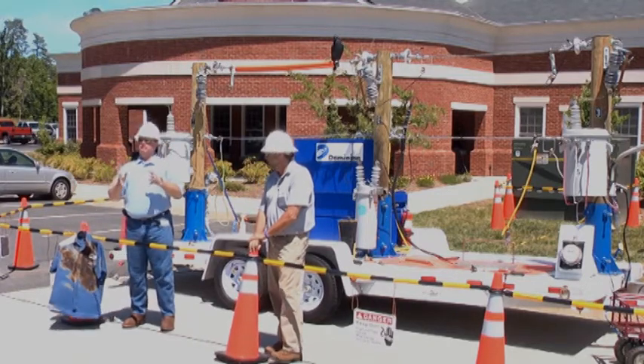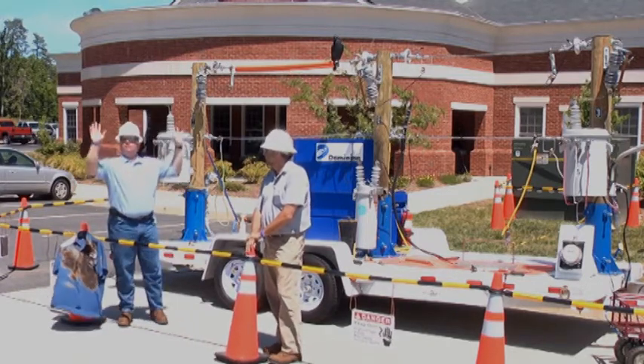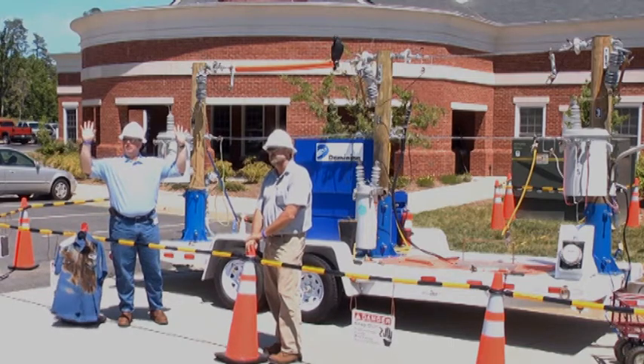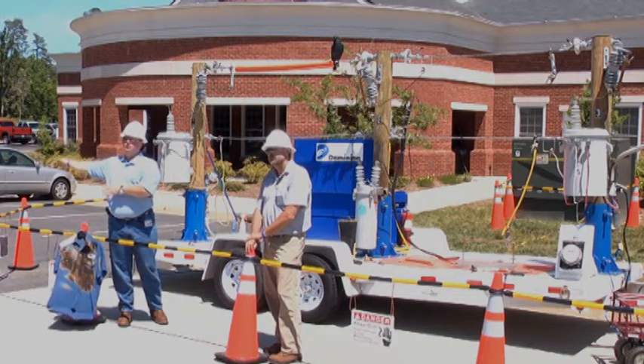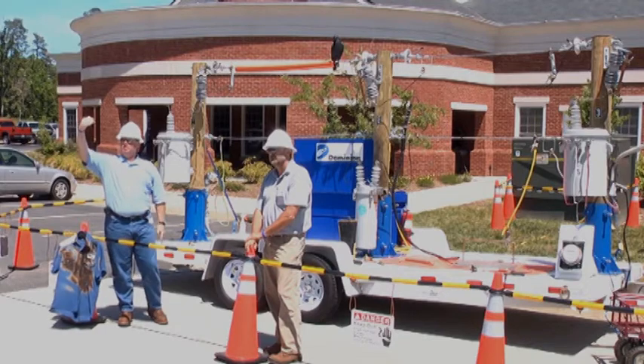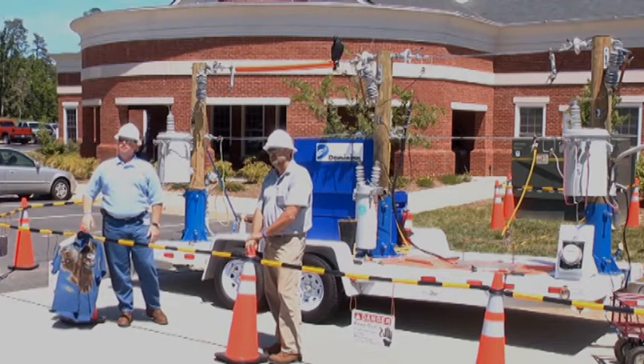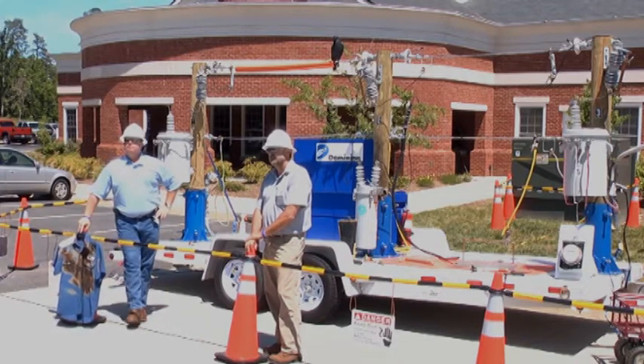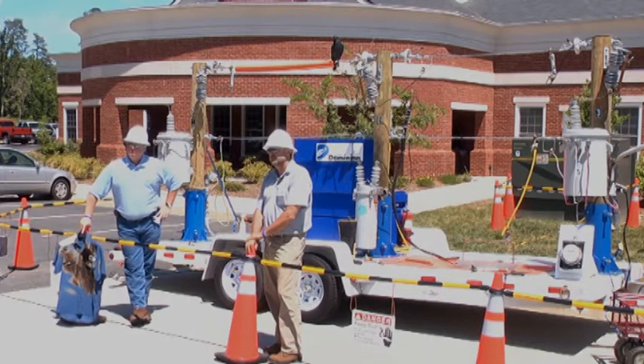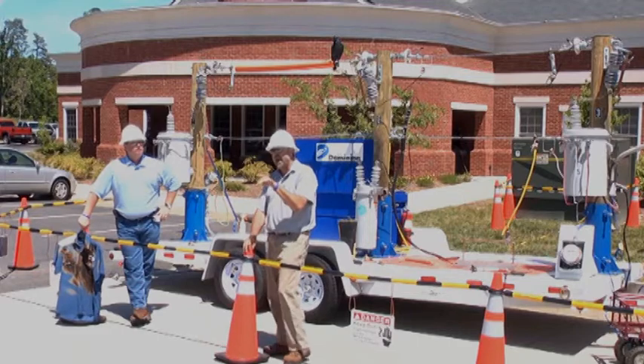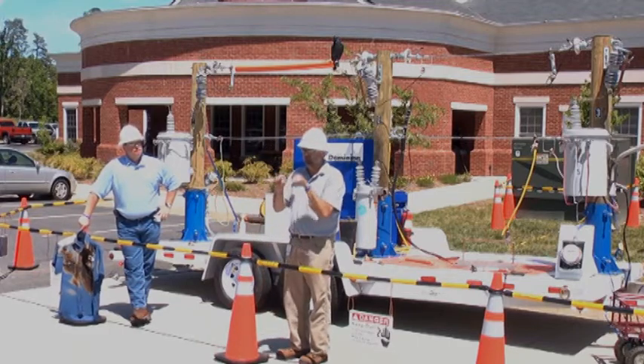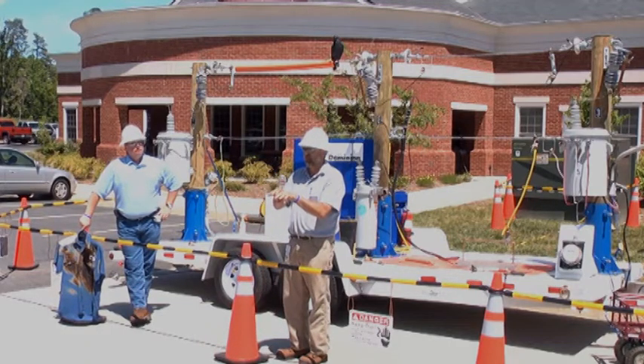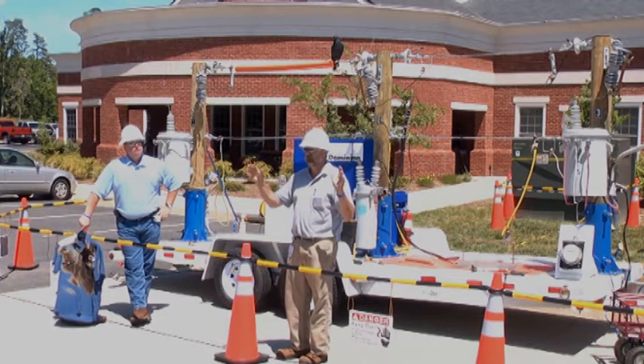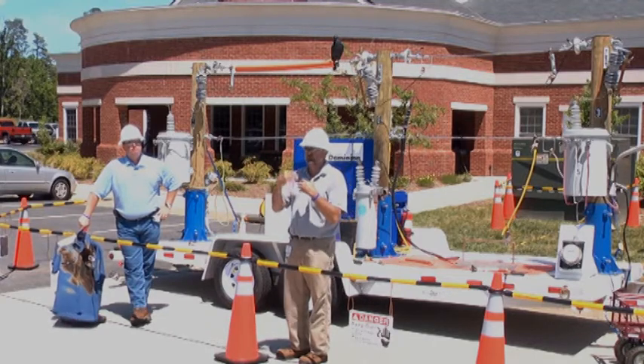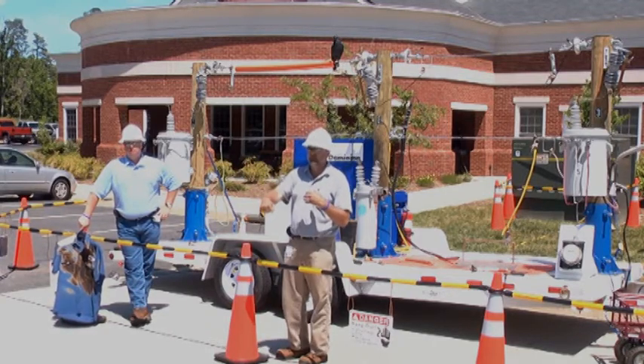You may have a down telephone line, and you look up and all of our lines look like they're in good shape. But that doesn't mean that a mile or half a mile down the road one of our power lines couldn't be down and get into that telephone line. My rule of thumb is always assume that whatever cable it is, it could be energized further up the road. You're exactly right. And if it's high impedance on those lines, they'll stay energized and won't operate our protective devices. Our system will just see it as load and keep pumping juice into it.